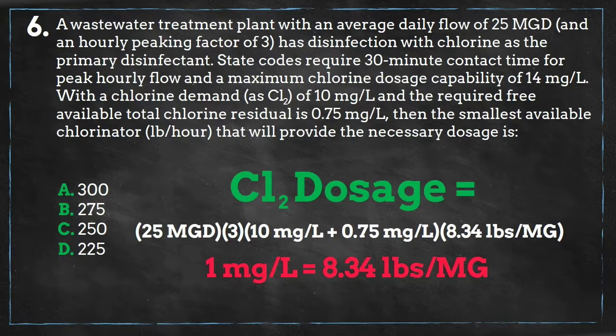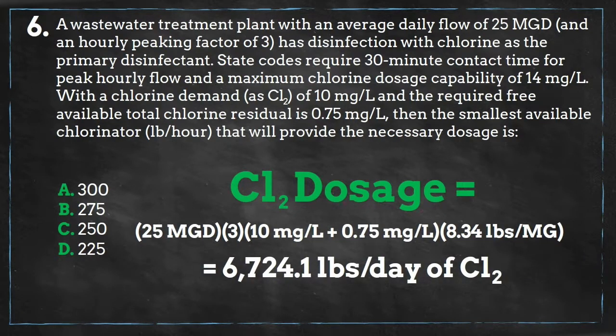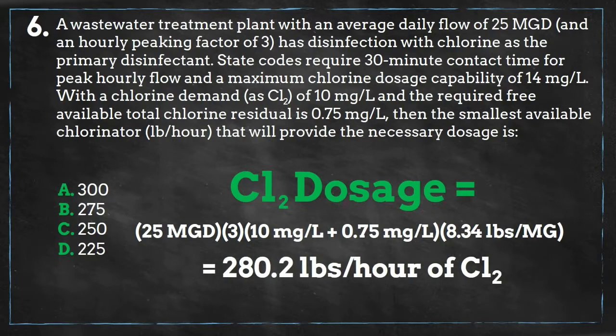We'll use the unit conversion of 1 milligram per liter equals 8.34 pounds per million gallons, and we get an answer of 6,724 pounds per day of chlorine. Converting that into an hourly rate, we get 280.2 pounds per hour of chlorine.